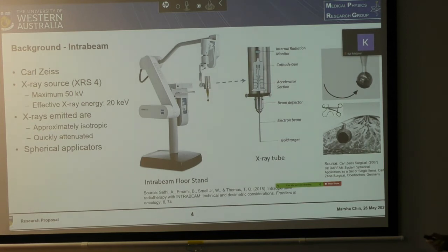So this here is the Intrabeam device that I'll be using. It's manufactured by Carl Zeiss, which is a German company. The maximum voltage is 50 kilovolts, which means the effective X-ray energy is about 20 keV. So this machine differs to conventional low kilovoltage systems because of these 2 points here.